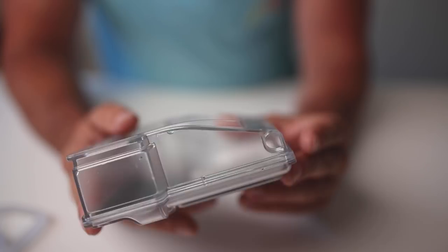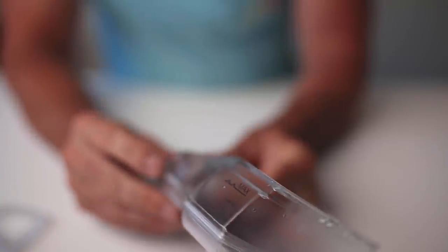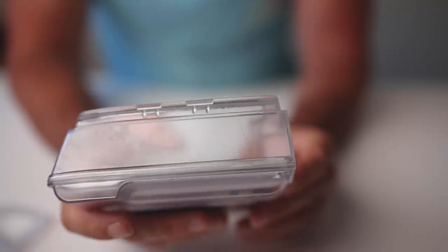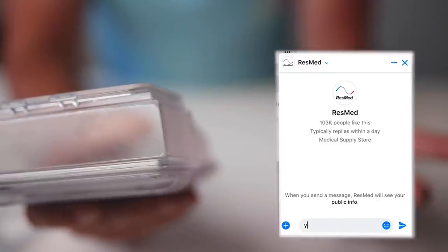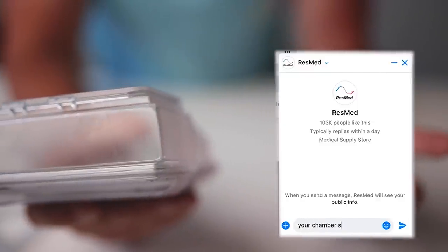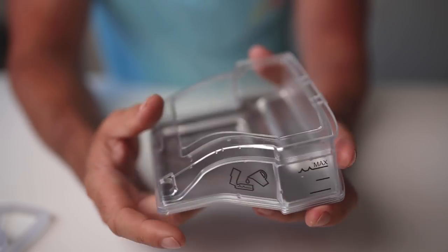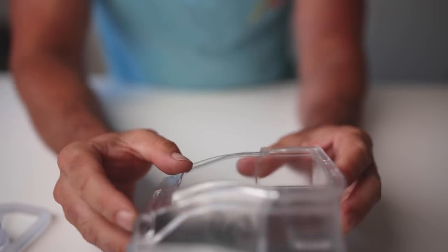That's why I've seen all sorts of people try and fix them. I've seen guys on YouTube getting food grade silicone and running around the side. That seems to work, there's some other fixes as well. I don't think you should fix them. I think you should contact ResMed and say your chamber's faulty, it doesn't work right the way it's supposed to, and get them to send you out another chamber. That's what I think the fix should be.